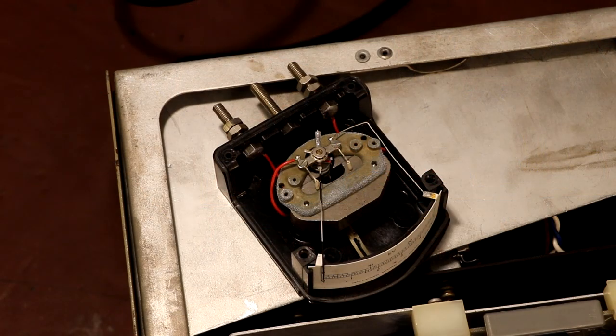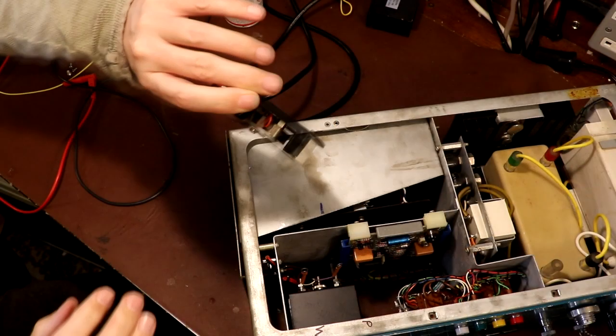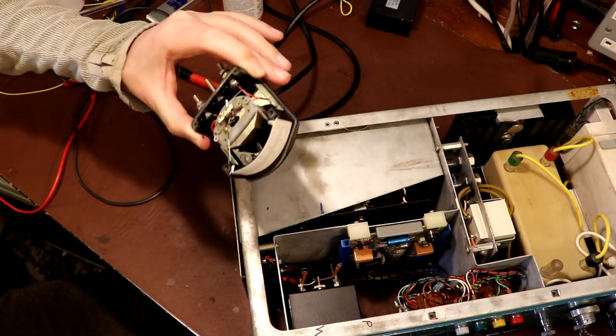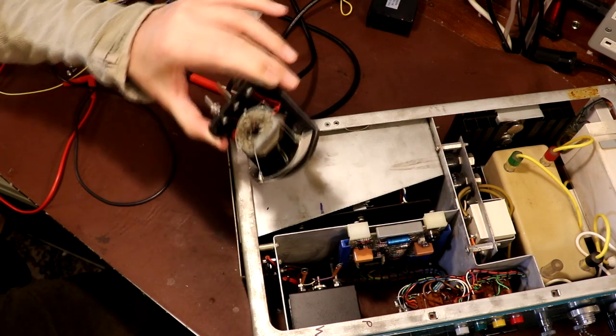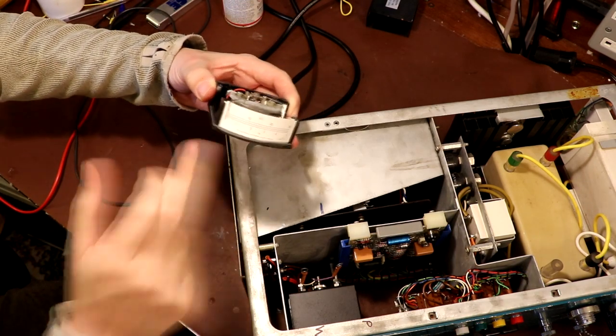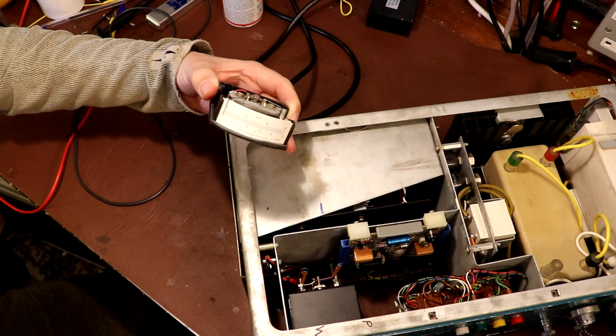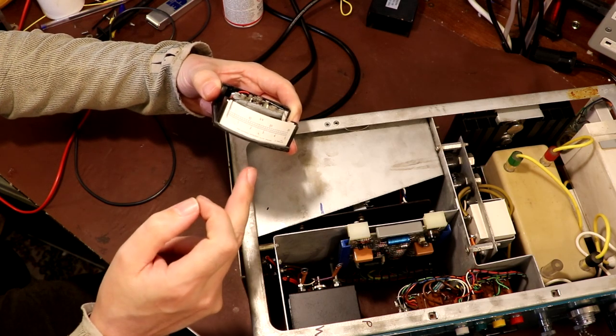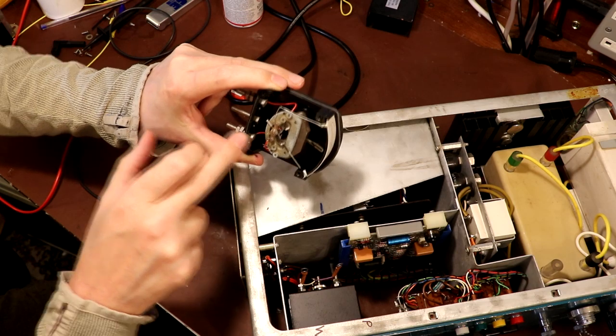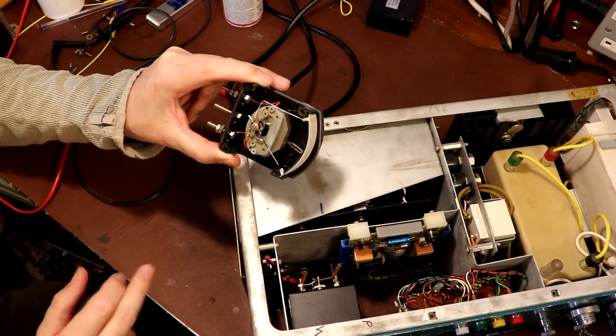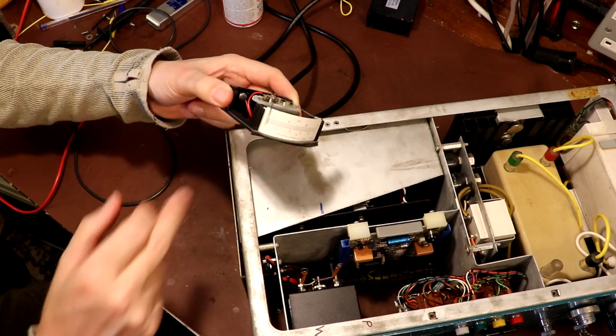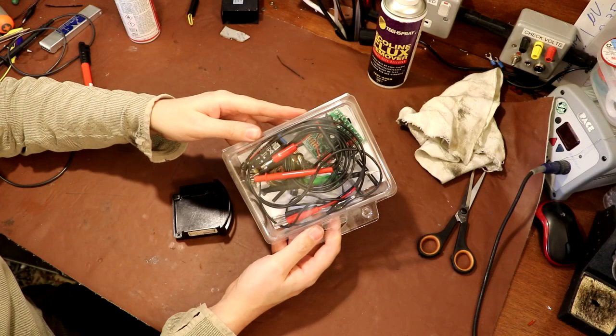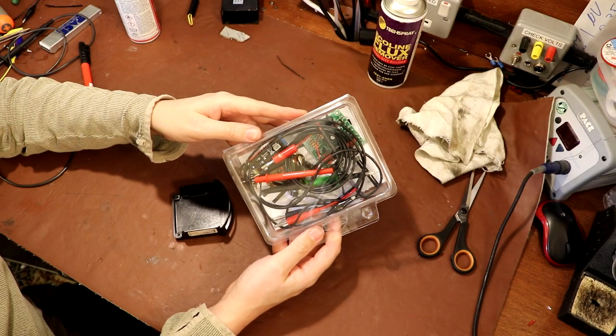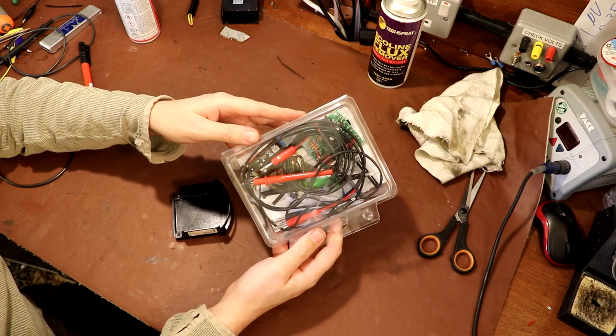So there's a crafty look at this meter for all you meter aficionados. You can actually see some bits of fluff floating around in there. And of course that's another problem with having the glass missing from the front of it, because if we get any kind of contamination, it can find its way into this very fine meter movement and it'll jam it up. So you really shouldn't ever run a meter without a front cover on it. Well, I think that we're actually going to need this Velleman signal tracer to repair this meter. So here we go.